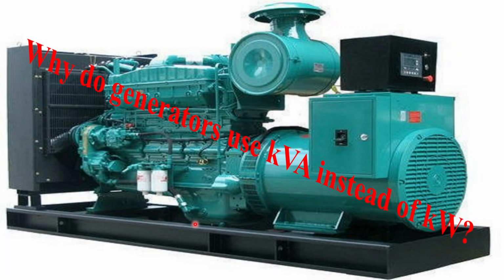The second reason is the load variability. Loads can be resistive, inductive, or capacitive, affecting the power factor. A generator must handle the varying power factors because the total apparent power, kVA, determines the generator's capacity to supply power under different load conditions. Rating generators in kVA ensures they are sufficiently robust to handle the total current demand, including both real and reactive components.